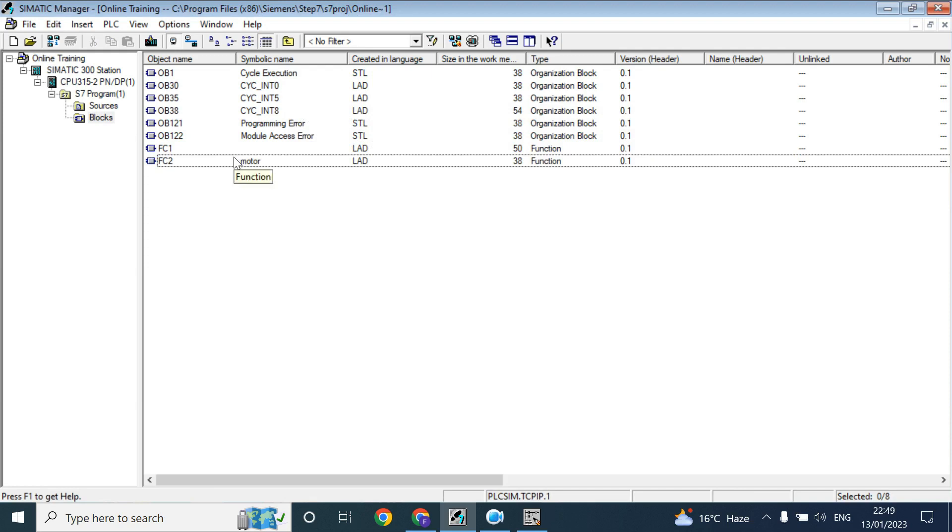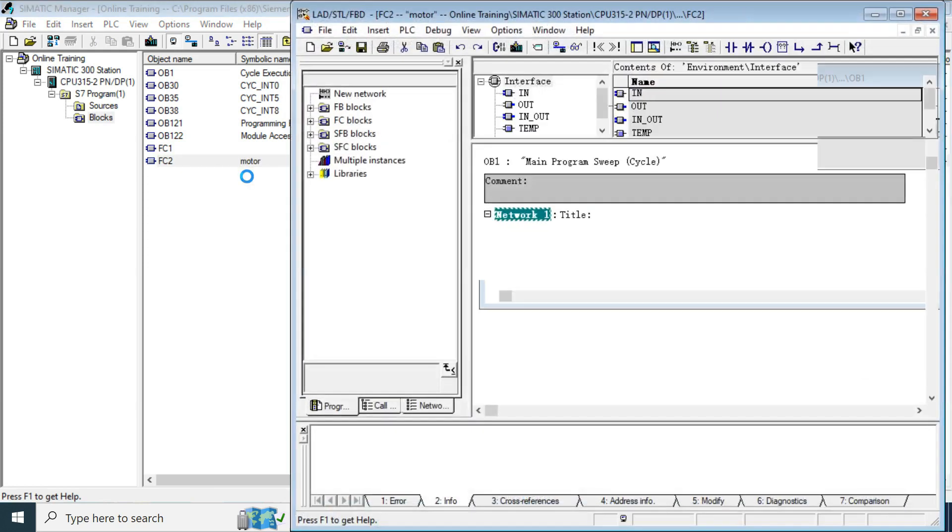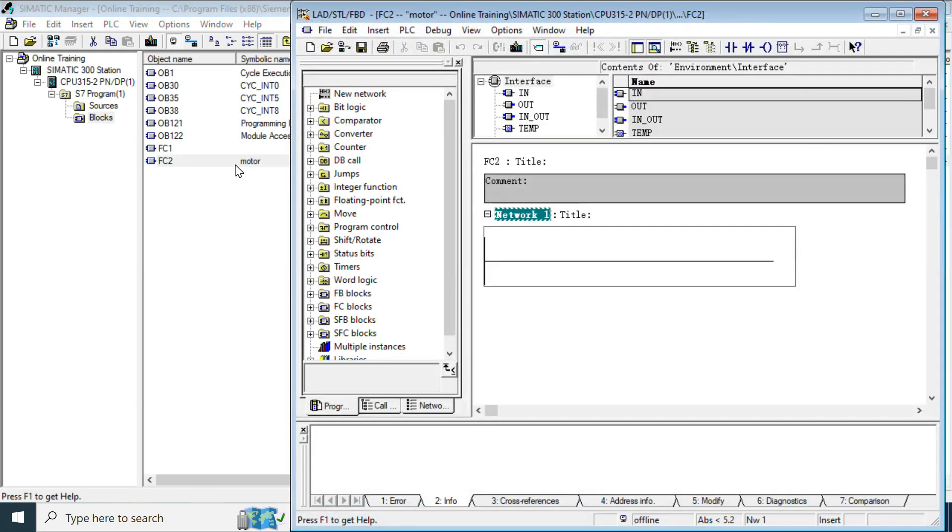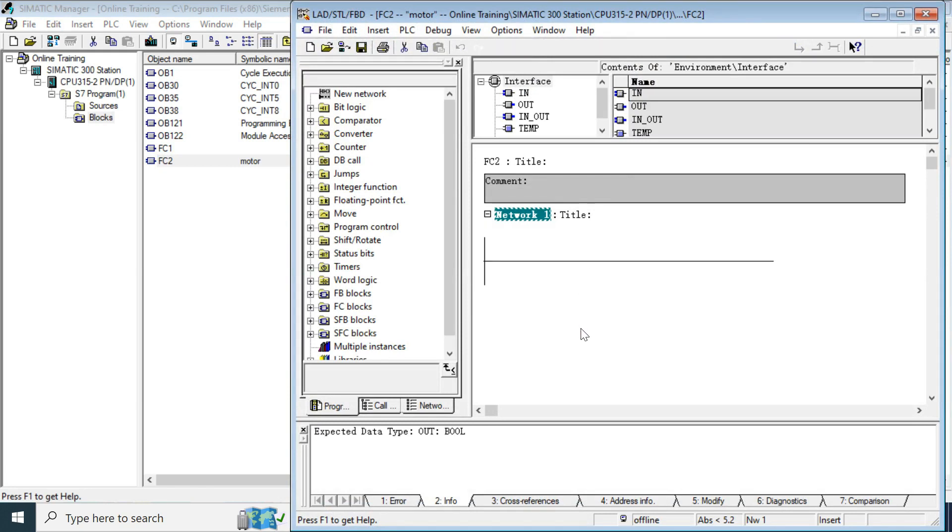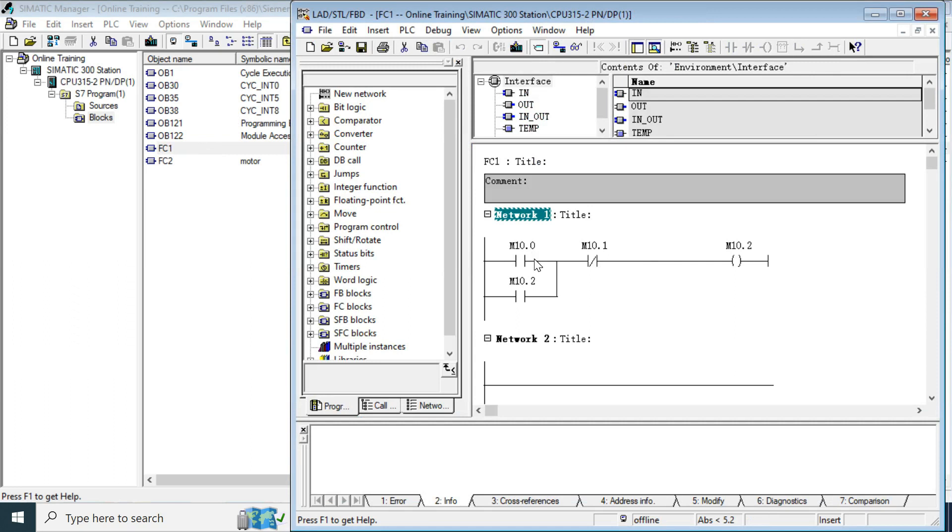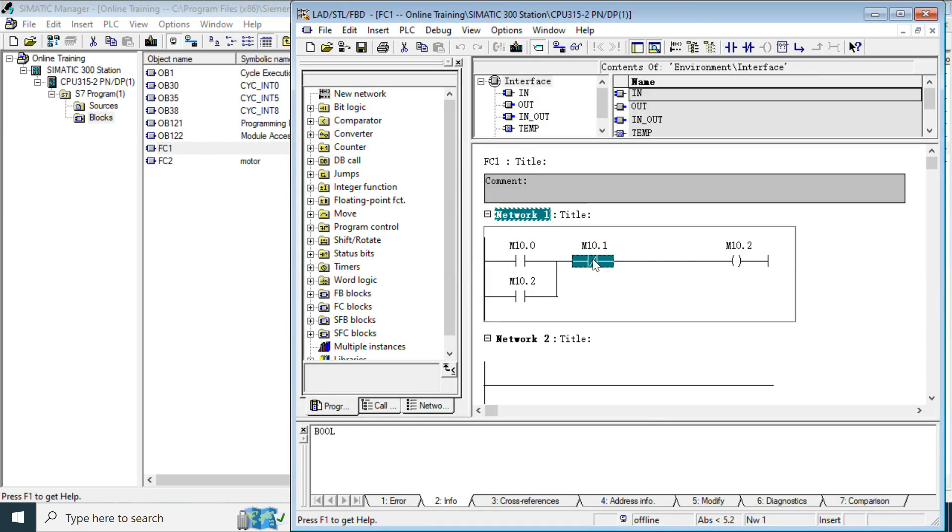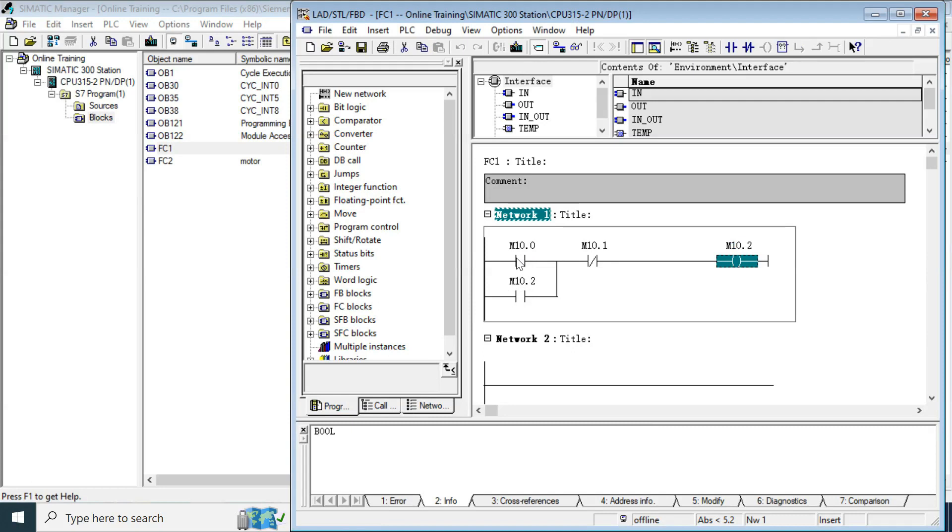Now, here, if you create the logic here, such as like this function, M10.0, M10.1, M10.2, here I have written as the simple DOL start. This is a stop button, start button and this is the output coil. And here we have hold the command when you release the start, it will hold by the output coil.